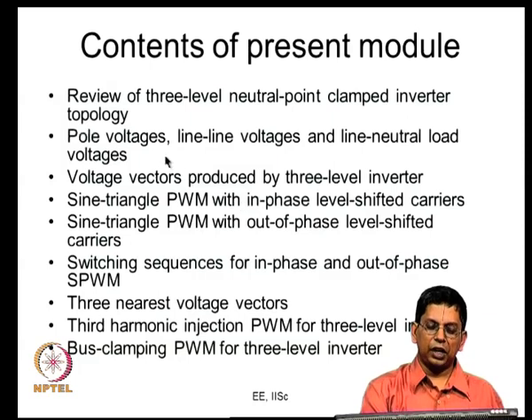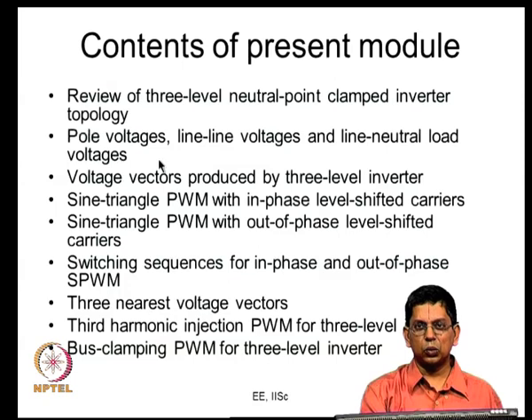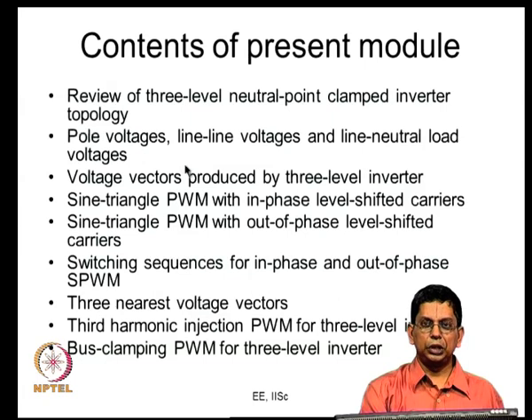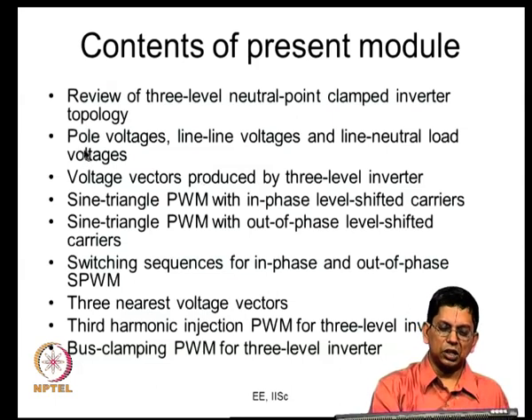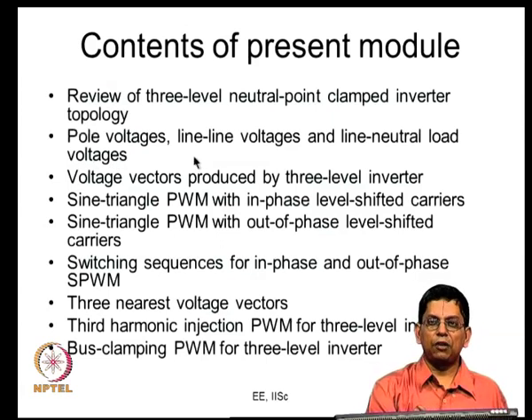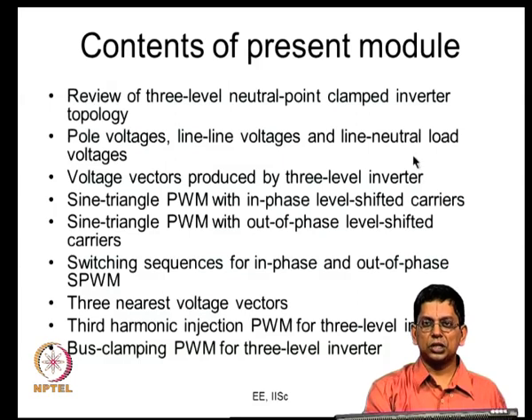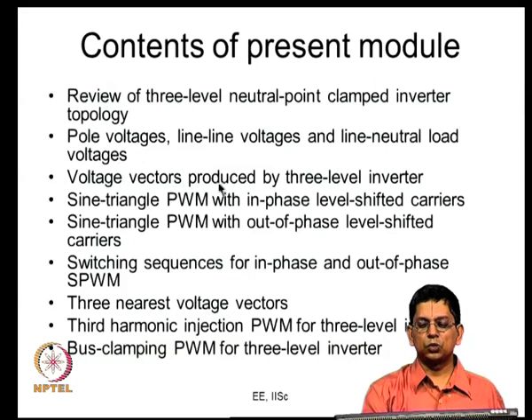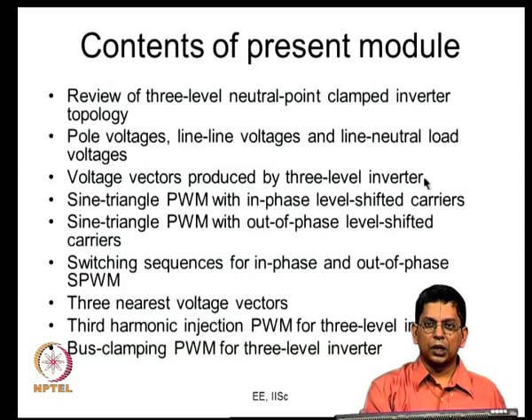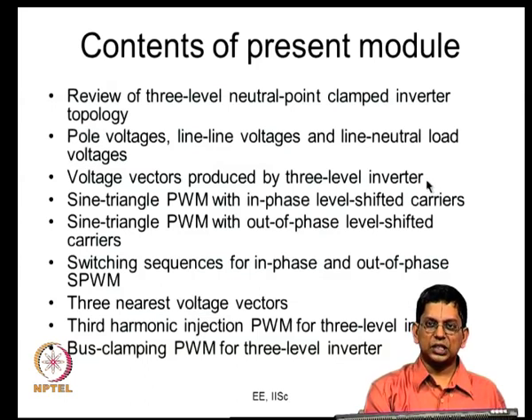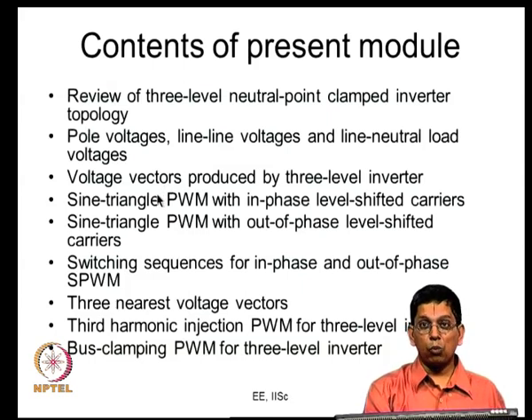Voltage vectors are produced by 27 inverter states. Once you understand the two-level inverter, dealing with the three-level inverter is not a problem. In a two-level inverter we have 2³ = 8 inverter states; here we have 3³ = 27. The two-level inverter has 8 states producing 7 distinct vectors, while here 27 states produce 19 distinct vectors, meaning there is much more redundancy — more inverter states can produce the same voltage vector.